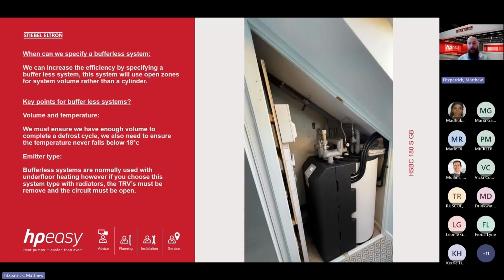And when can we specify bufferless systems? So we can specify bufferless systems if we have the same type of heat emitter. Excuse me, we can have two zones. So you can have a ground floor and a first floor of underfloor, or a ground floor and first floor of radiators, but they need to be the same heat emitter type or the same flow temperature. So if the radiators can be sized to 38 degrees, sorry, no, my apologies. Yes, so it's the same heat emitter type, so they have to be underfloor or radiators. Even if you size the radiators to 38 degrees, the same as the underfloor, you will still have different flow rates. So you would need to have a buffer cylinder for that system.